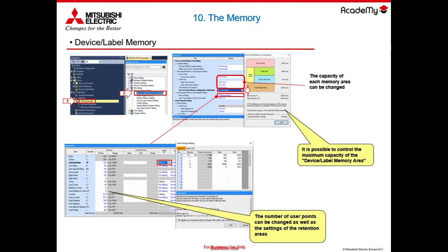From the moment, for example, there is the need to increase the portion of memory for the labels, we will have to repartition. So we remove, for example, from the device area what we intend to add to the label area. That is in the end the sum of these areas. However, in the case of an R04 it remains 200 kwords. So about 400 kbyte.